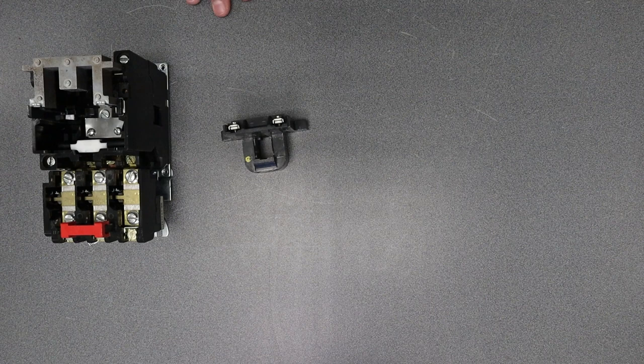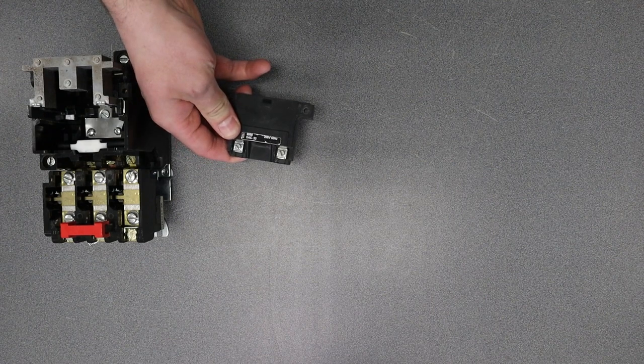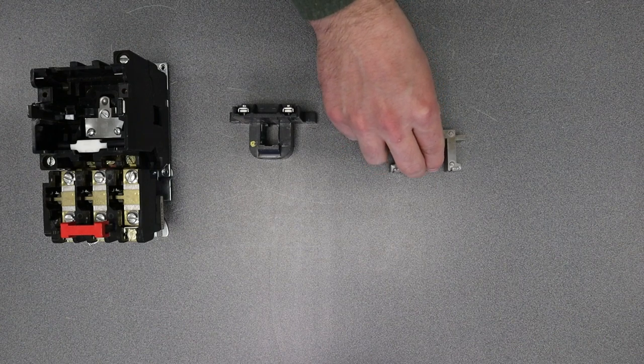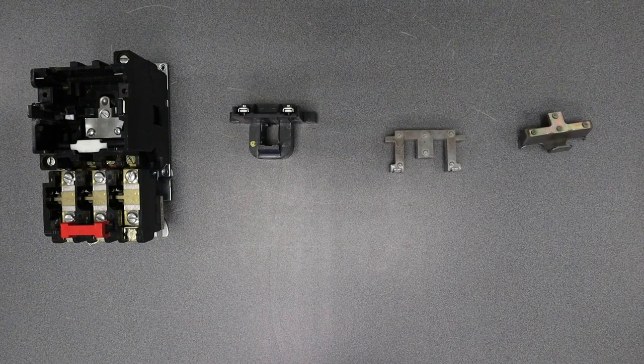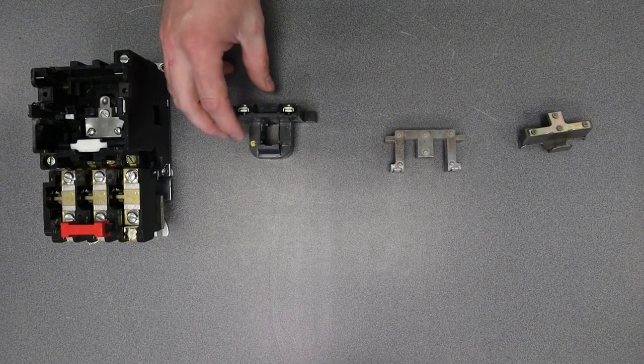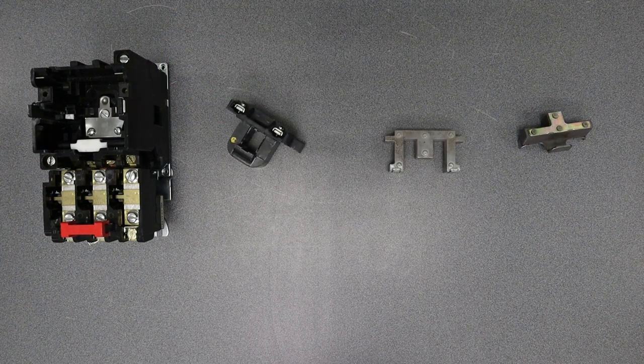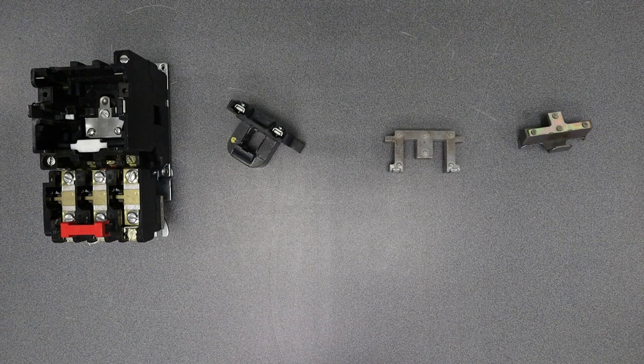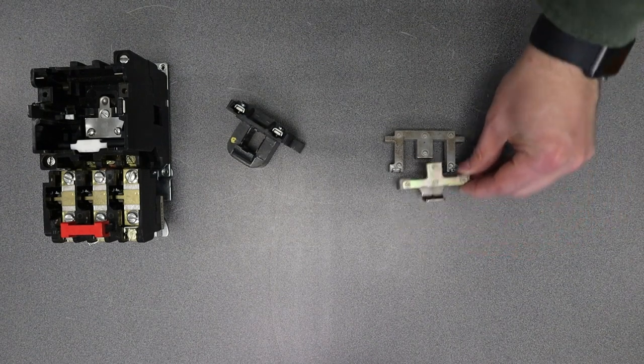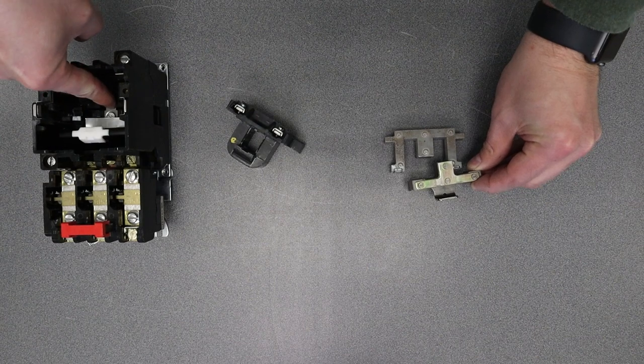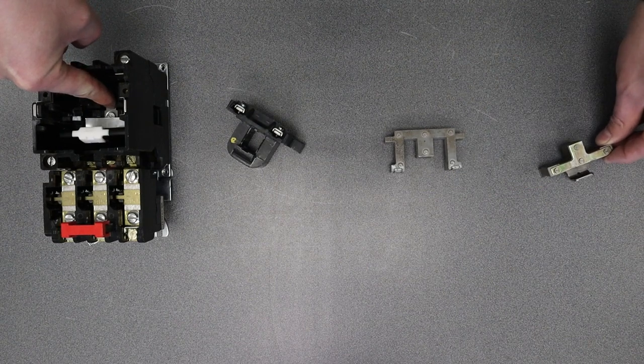I have got my coil. This one happens to be a 208 volt coil. I have got a core and I've got an armature. So we know that the coil wraps around the core. When we energize the coil, it turns into an electromagnet and pulls the armature down, which will change state of all the contacts in that contactor.